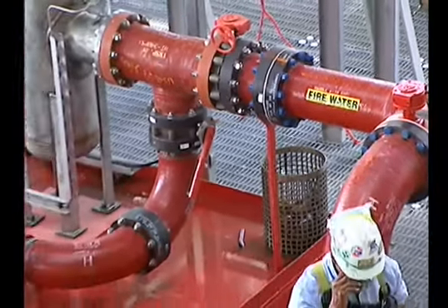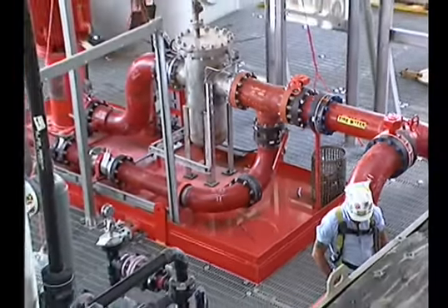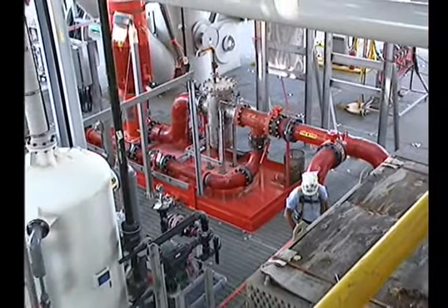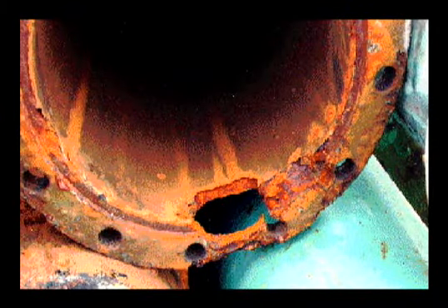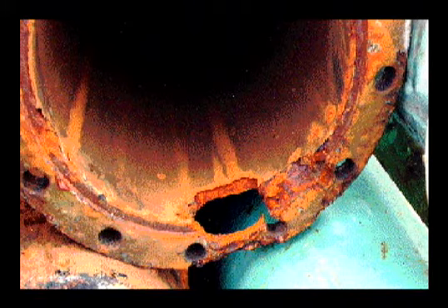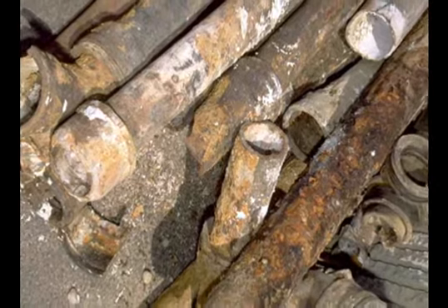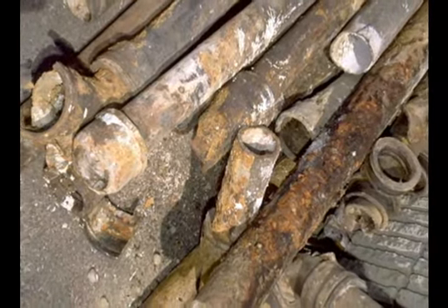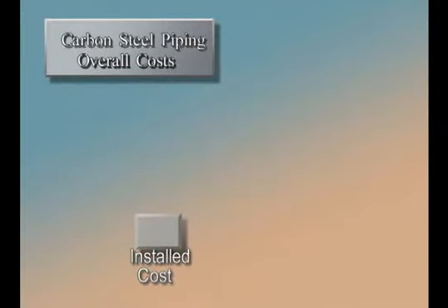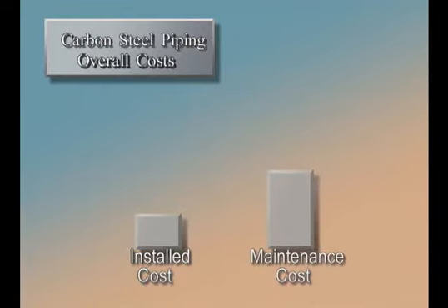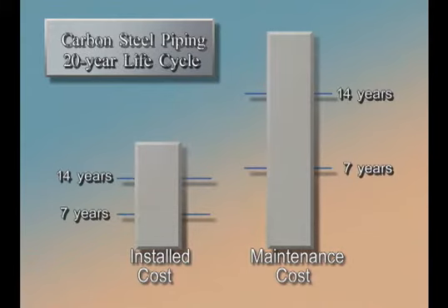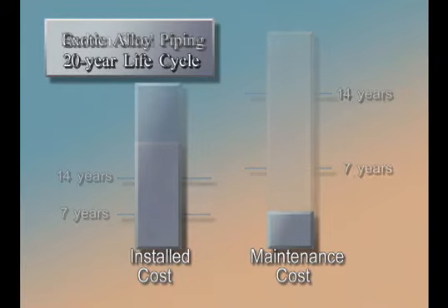Fire mains are regularly flushed to minimize this problem, but the sprinkler system itself is difficult to flush. Cooling water systems, fire mains, and deluge systems intermittently exposed to salt water during regular tests experience even more rapid corrosion. In time, the entire system can become undependable. Although initially inexpensive, carbon steel piping can be expected to double its installation cost in maintenance expense over a 20-year life cycle. It will also require complete replacement as often as every 7 years in a highly corrosive environment.